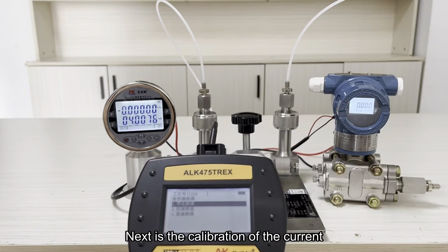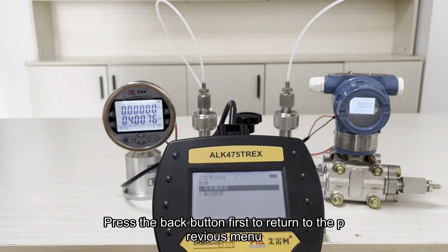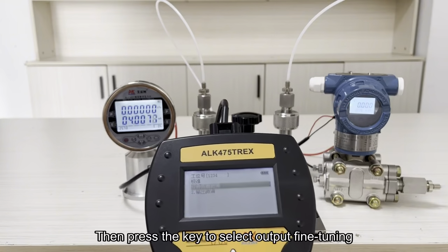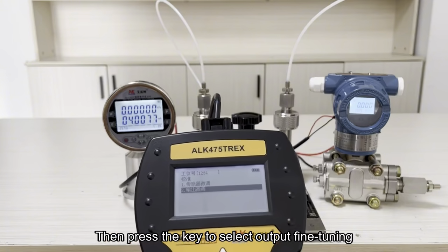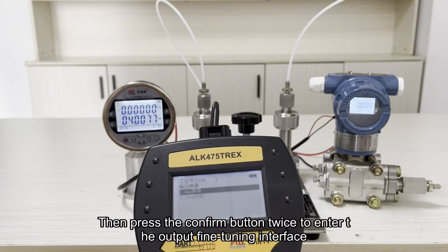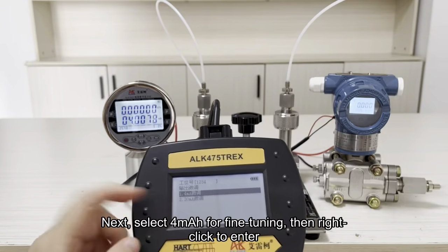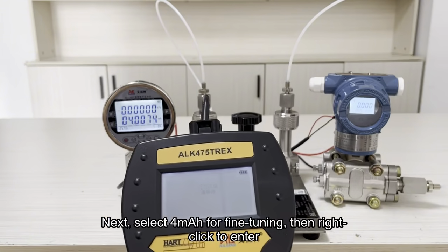Next is the calibration of the current. Press the back button first to return to the previous menu. Then press the key to select output fine-tuning. Then press the confirm button twice to enter the output fine-tuning interface. Next, select 4 mA fine-tuning, then right-click to enter.